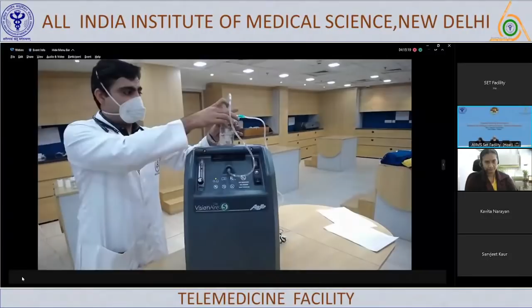Traditionally it is used for chronic care or home oxygen support, but it can be used even in acute care when the facilities are not available. Limitations are that it has a limit on flow. In some machines it can go up to 10, but usually the flow is up to 5. It can be used with a face mask, a venturi mask or a nasal prong, but it cannot be used with a non-rebreathing mask.